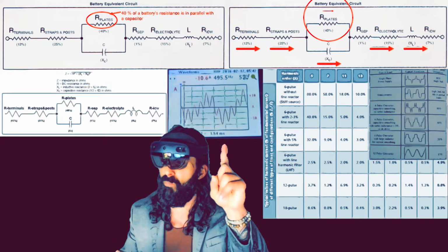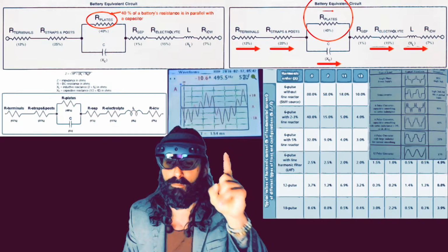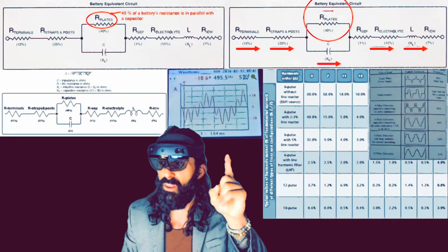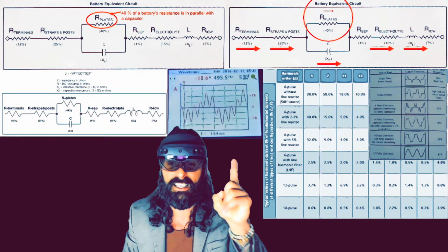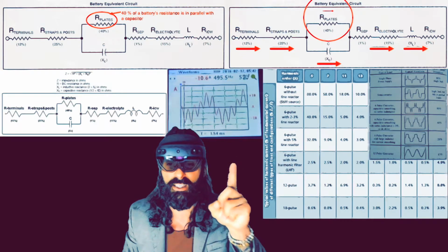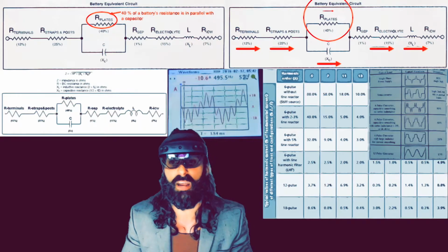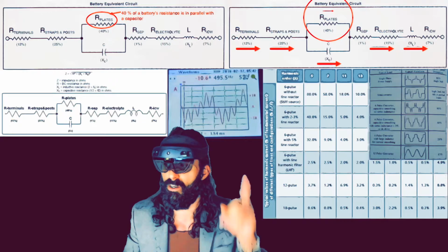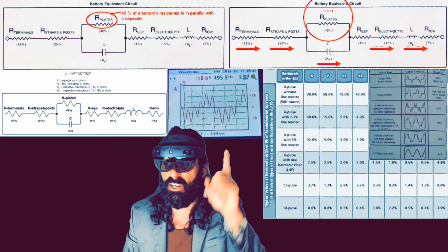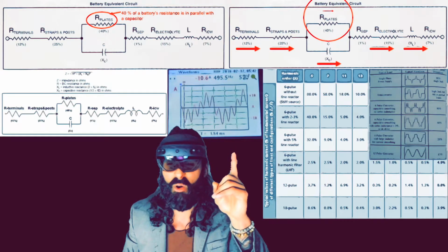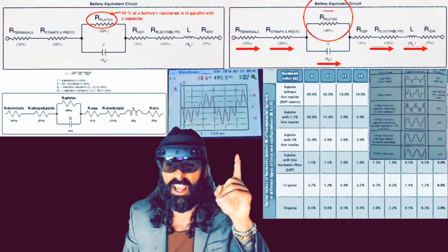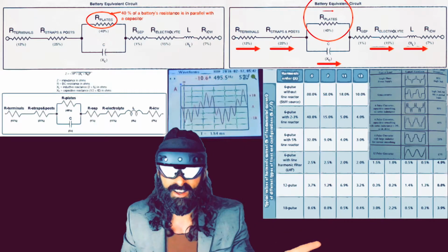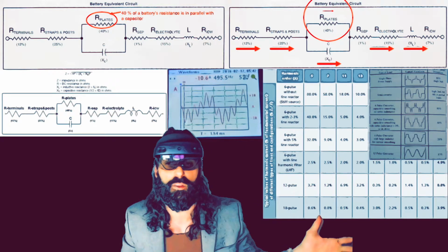What you see right above me is an actual noisy DC bus signal on a 750 kVA UPS, 3-phase power. There's an 11 amp AC signal harmonic riding on the DC bus. So let's come back to impedance again, which is injecting an AC current essentially through the battery system. If it's using a 1 amp signal on the battery bus, how is it going to differentiate that signal from the noise floor? The answer is very clear: it cannot. So they don't know that when they implement that out in the field.